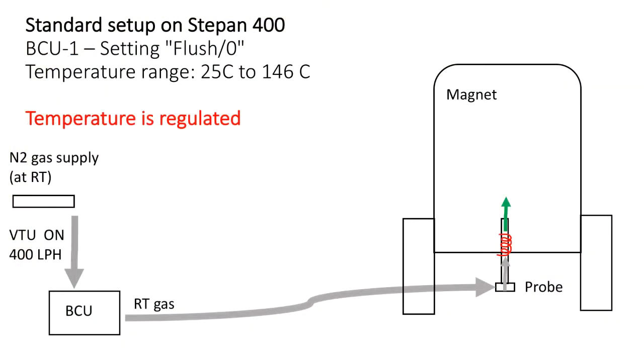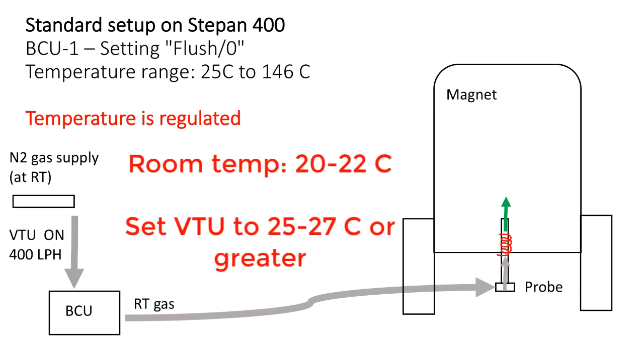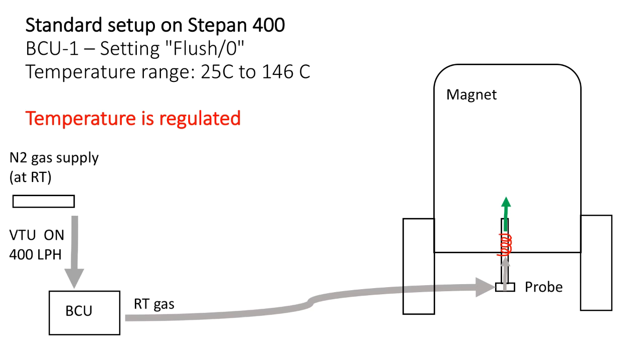When VTU is turned on, it begins supplying 400 liters per hour of gas to the BCU, which supplies it further to the probe, and the probe heater heats it up to the temperature necessary for the NMR experiment. The lowest regulated temperature for the experiment is about 5 degrees greater than temperature of the gas supply. With the room temperature gas supplied at 20 to 22 degrees C, we should set VTU to 25 to 27 degrees C or greater for effective regulation.